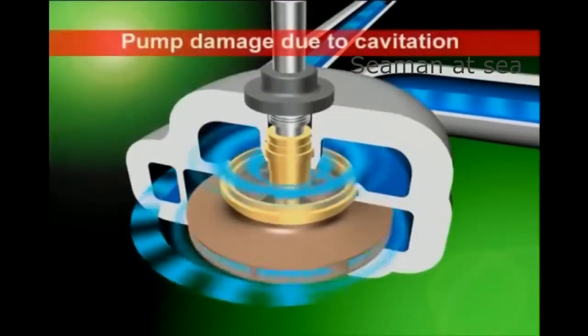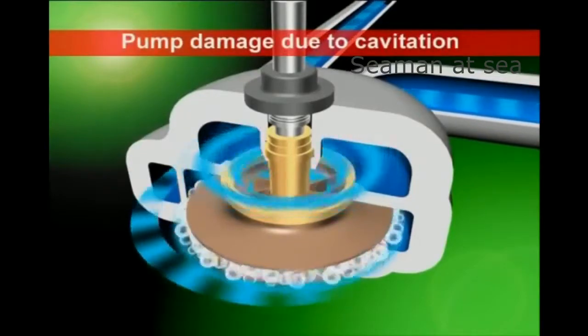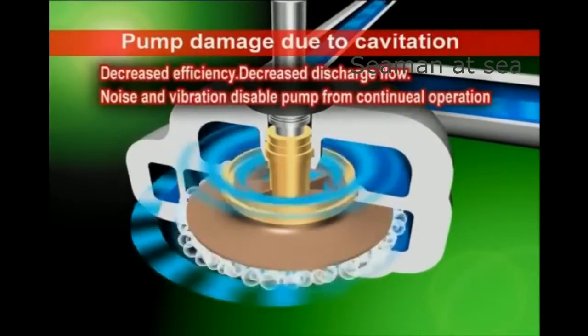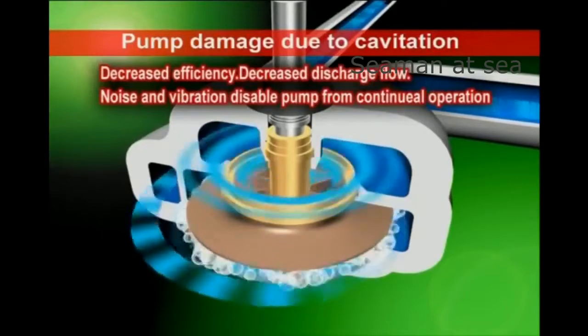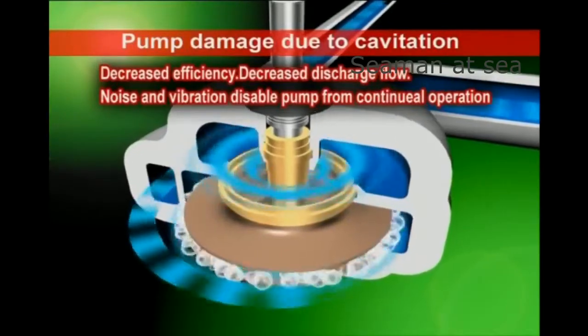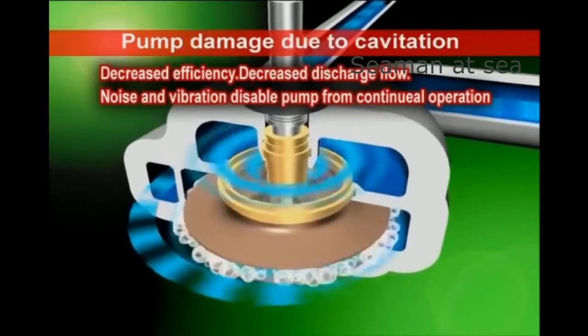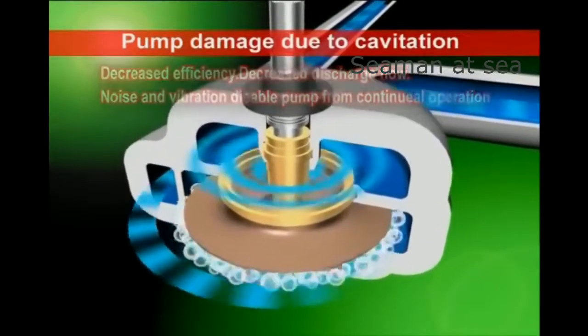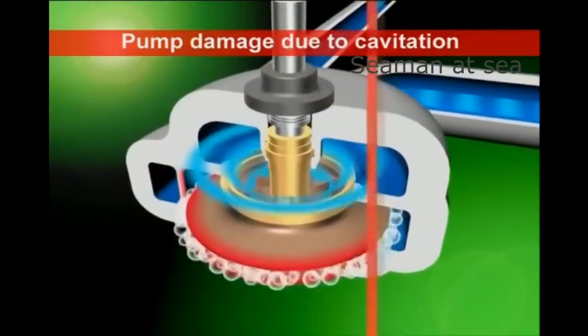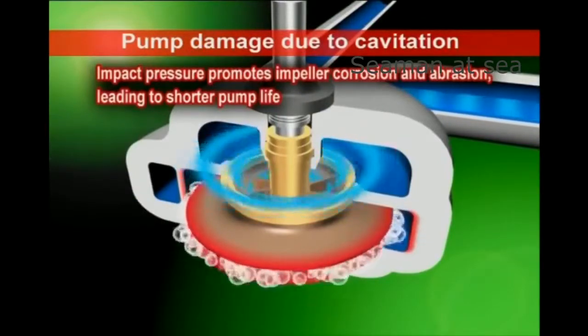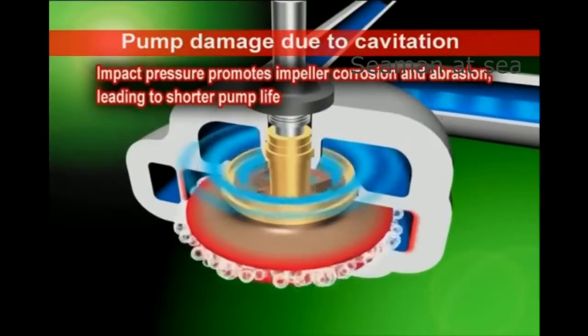Typical damage to pumps due to cavitation includes decreased pump efficiency, decreased discharge flow, and noises and vibrations which eventually make it impossible to continue operating the pump. Impact pressure promotes corrosion and abrasion of the impeller, leading to shorter pump life.